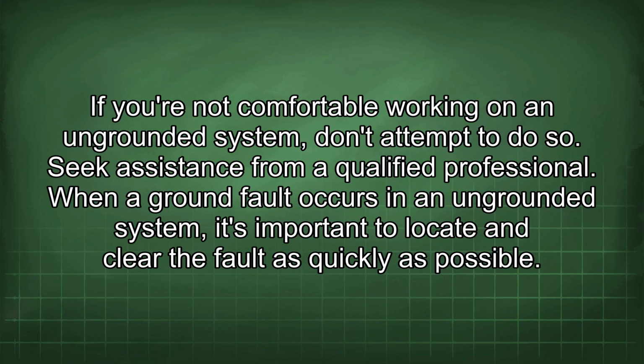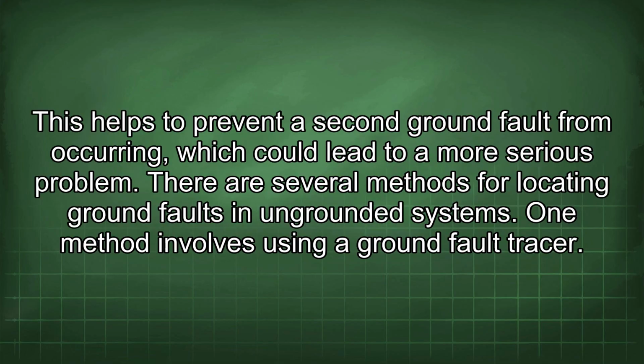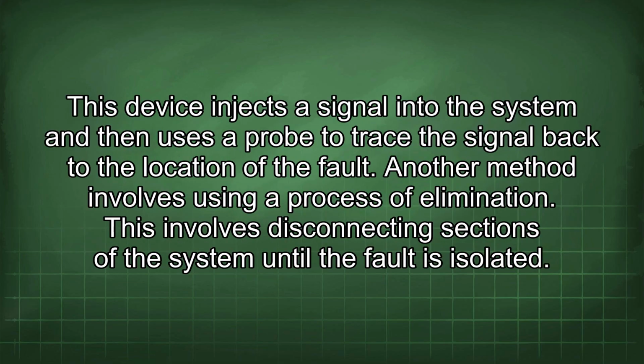When a ground fault occurs in an ungrounded system, it's important to locate and clear the fault as quickly as possible. This helps to prevent a second ground fault from occurring, which could lead to a more serious problem. There are several methods for locating ground faults in ungrounded systems. One method involves using a ground fault tracer. This device injects a signal into the system and then uses a probe to trace the signal back to the location of the fault. Another method involves using a process of elimination. This involves disconnecting sections of the system until the fault is isolated.